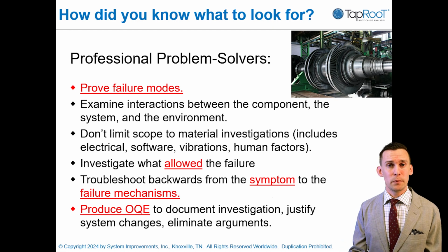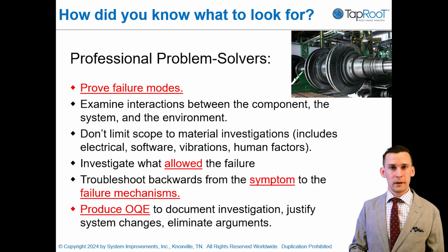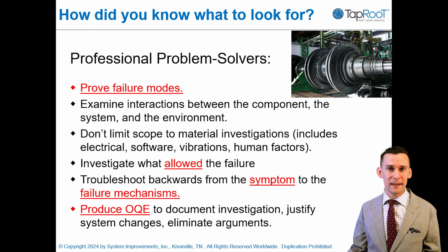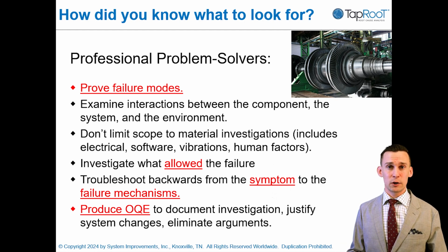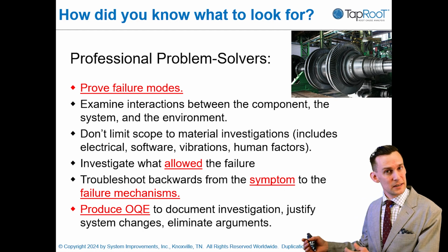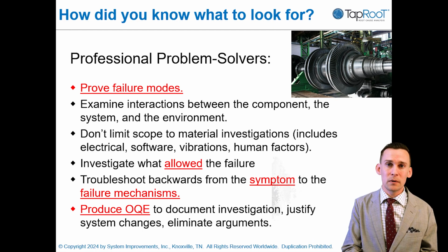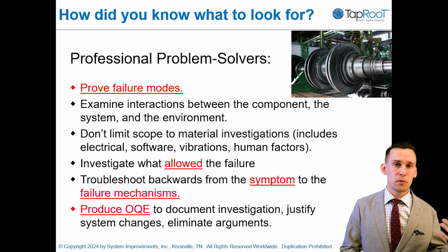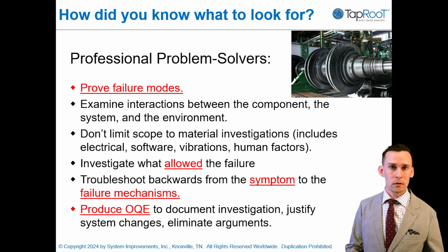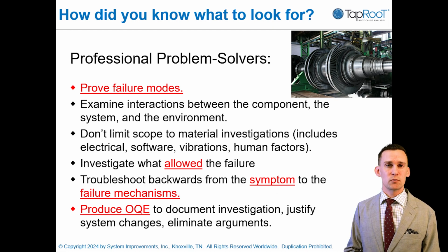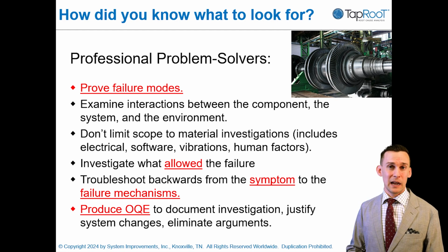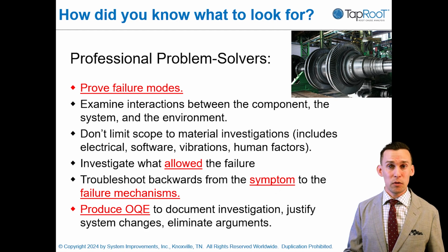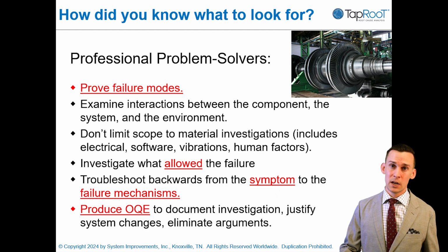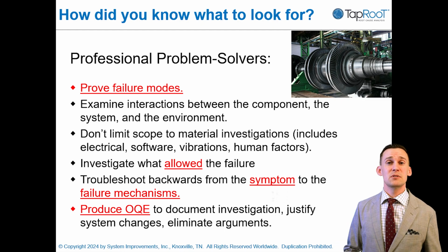You need to look beyond the component that failed. If my temperature and pressure are so high in my fluid system that it corrodes my carbon steel piping, sending all that grit into my pump, and the pump fails and I keep replacing it, my failure has absolutely nothing to do with the pump. The pump is running exactly as it should. I'm feeding things from upstream into the pump that are making it fail. So unless I understand how the pump failed and what is causing it, replacing it is going to buy me into the same situation.